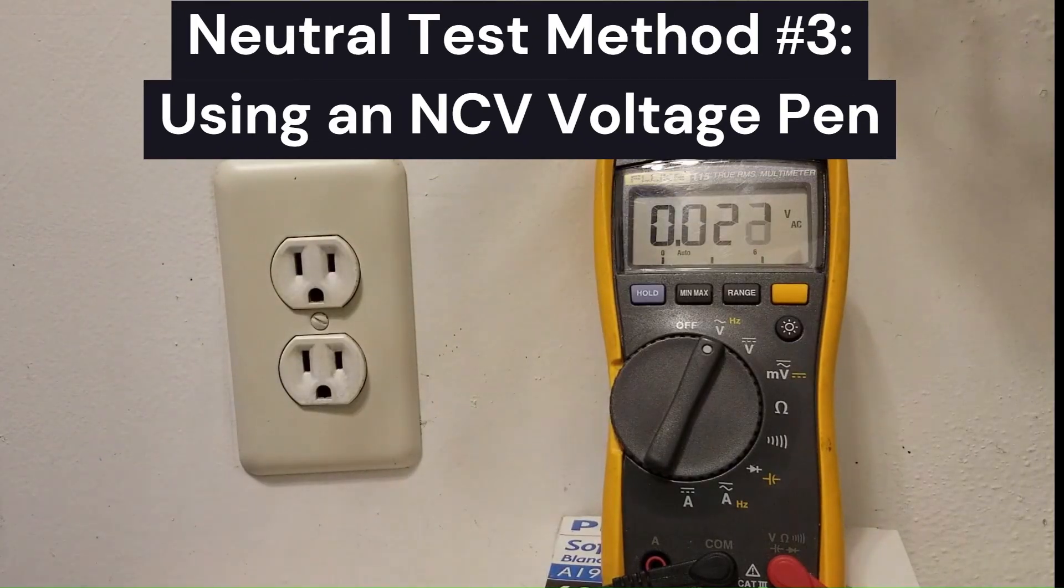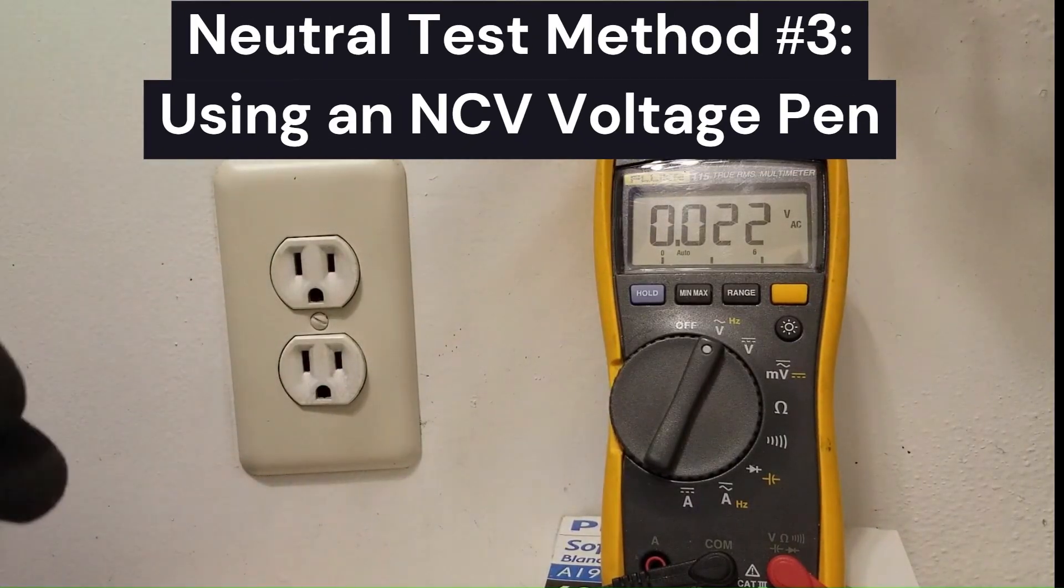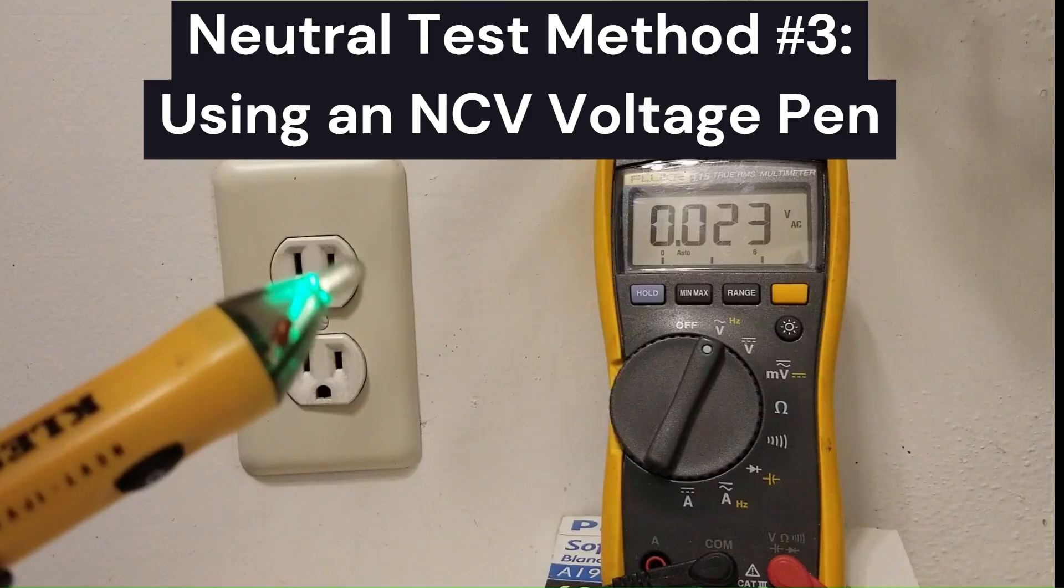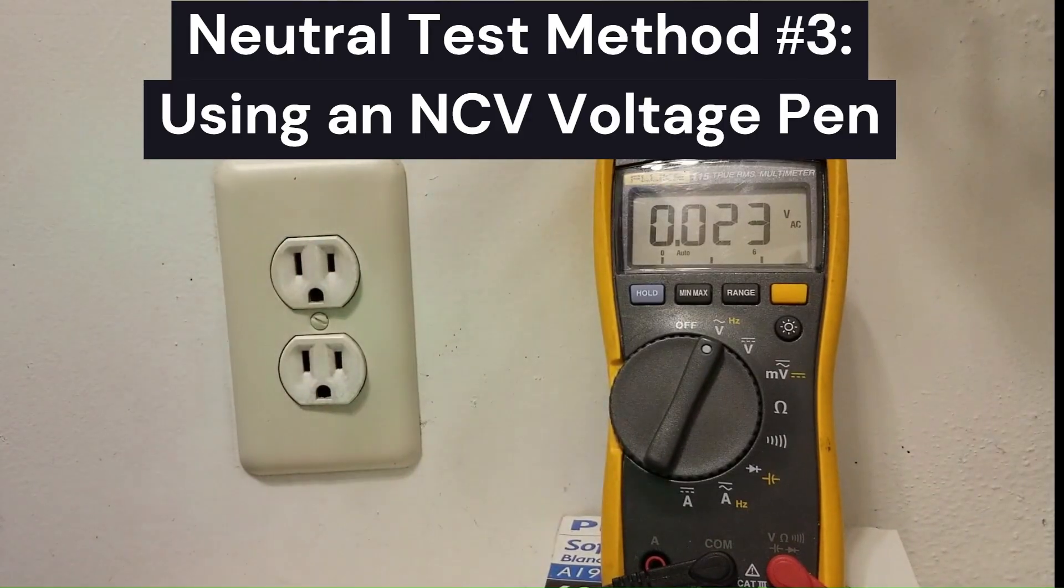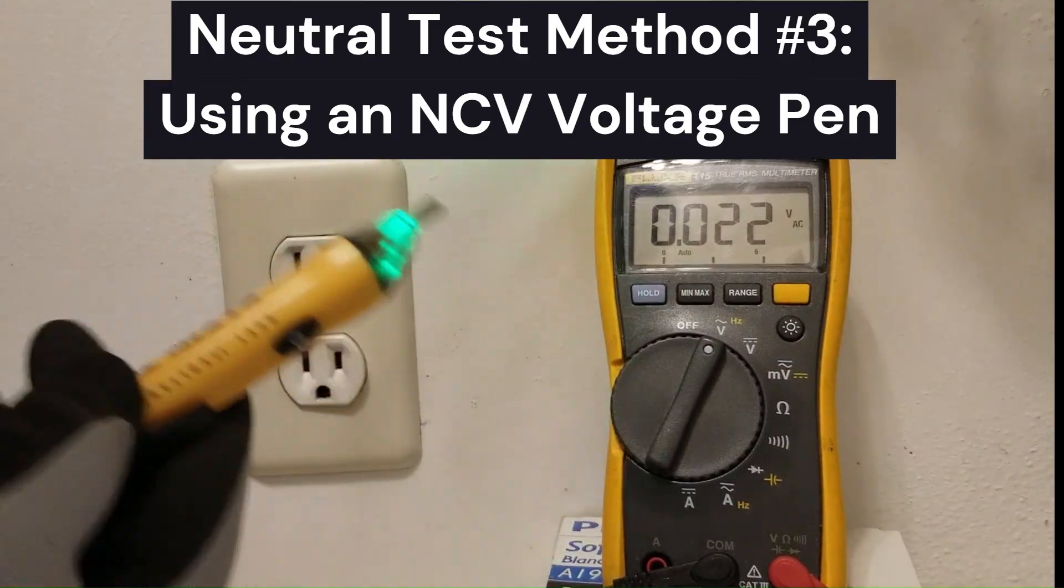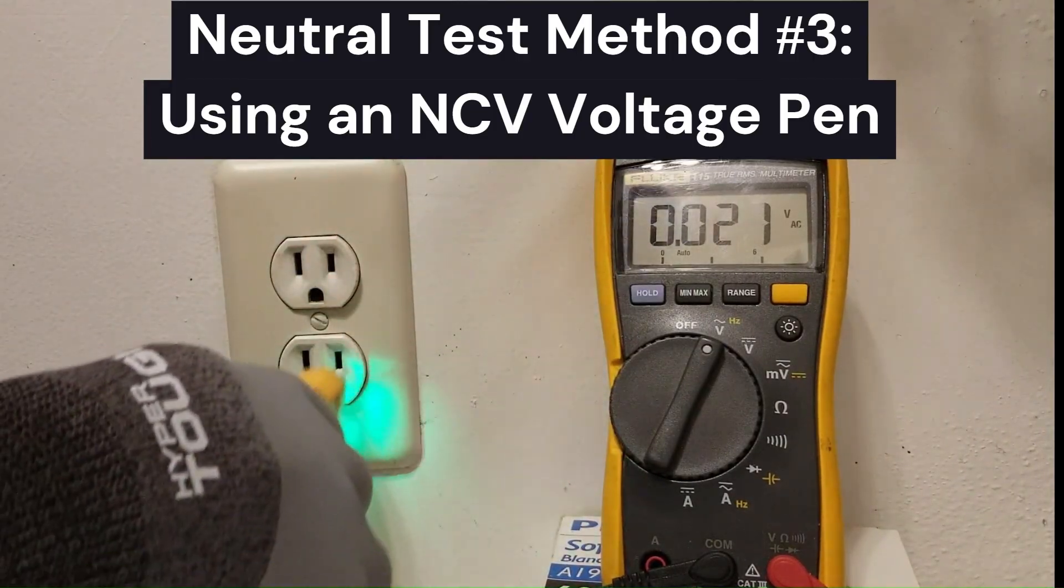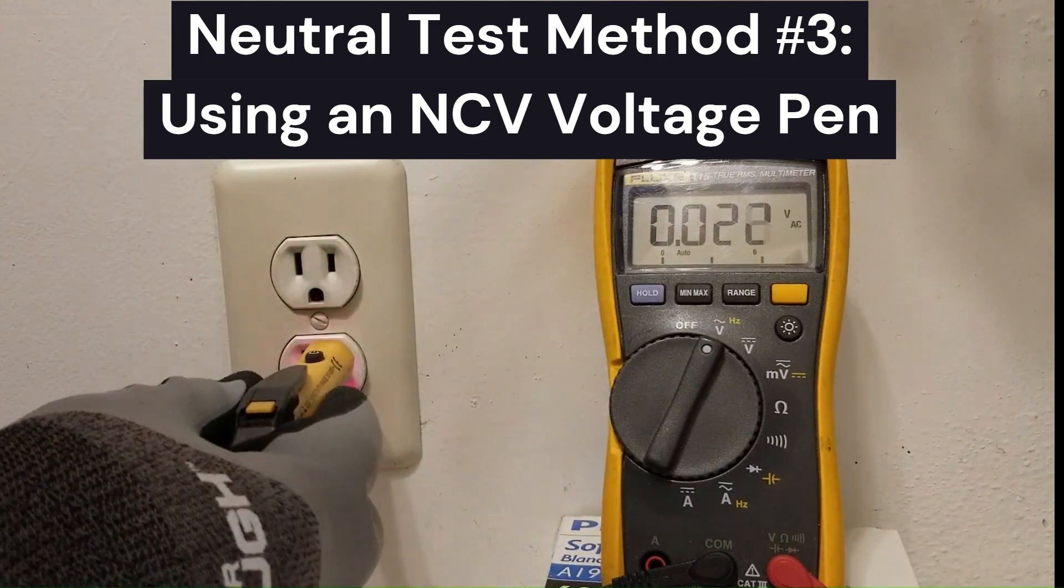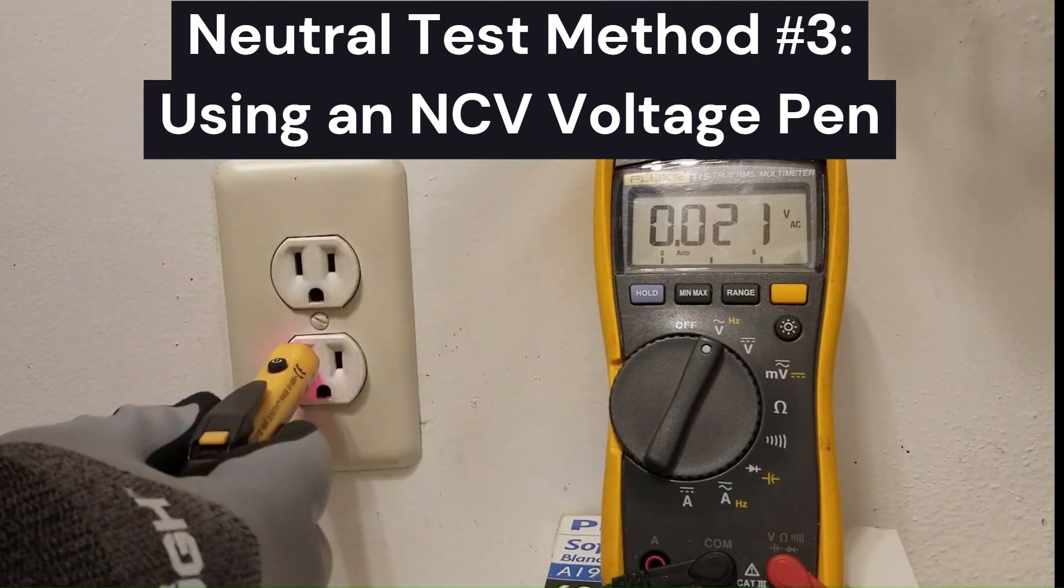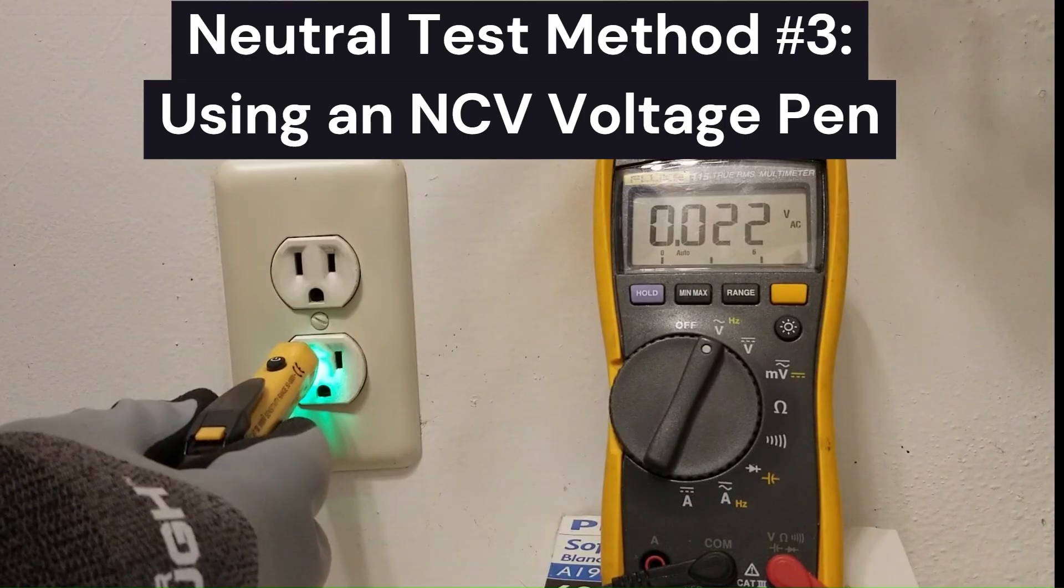So how can you tell if you only have a voltage pen? A voltage pen is a very handy way. If you know how to use it and you know how to interpret it, it can give you a lot of information. A lot more than most people think. So normally a voltage pen is going to give us on a good outlet a reading on the hot like this, which it should. And no reading on the neutral because neutral should be zero volts, right?